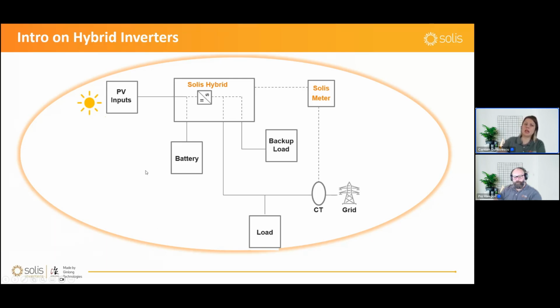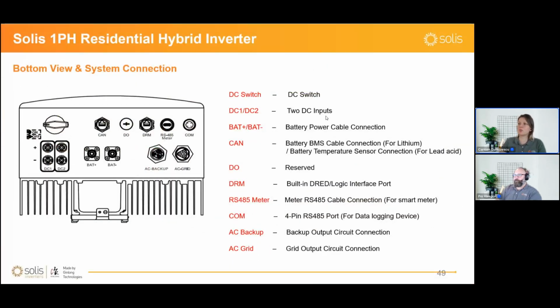And for example, in the nighttime, when you don't have PV energy available and you turn on your loads, this Solis meter will detect that there's consumption of energy coming in from the grid. So that's when it will start to discharge the battery so that it will cover those loads. So this is the normal self-use mode in which an inverter can work. Here you can see these are the normal.